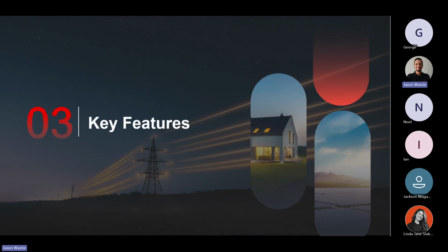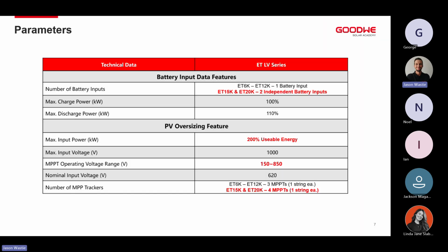So next we'll go through some of the key features for the ETLV series. As we go through these, we'll obviously see some of the slide pieces in red, so the pieces that I'll discuss. So with the ETLV, like I mentioned, we've got from 6 kilowatts all the way up to 20 kilowatts. Most importantly, we'll focus on the 12, 15, and 20 kilowatt units. The 12 kilowatt unit has got one battery input. The 15 and 20 kilowatt units have got two independent battery inputs.